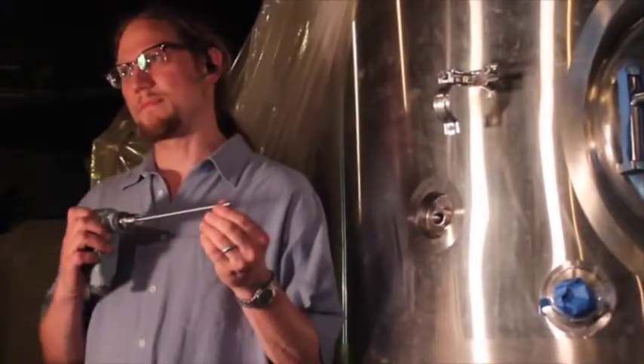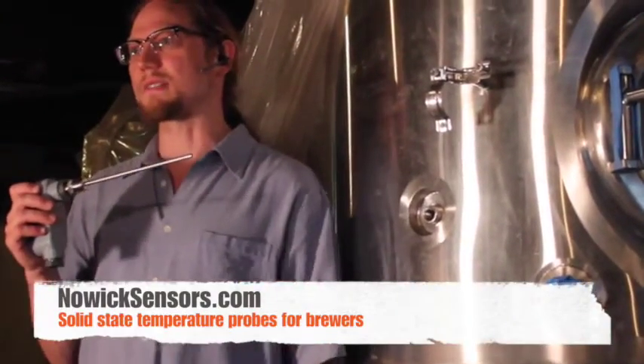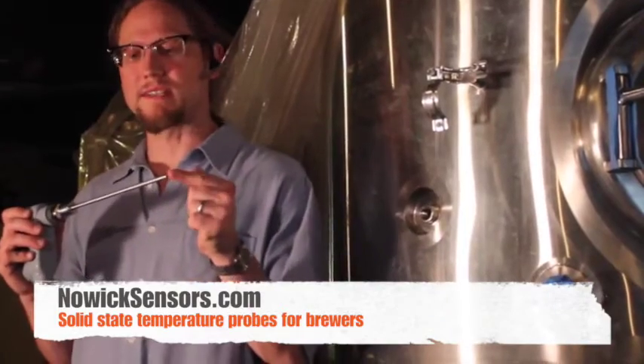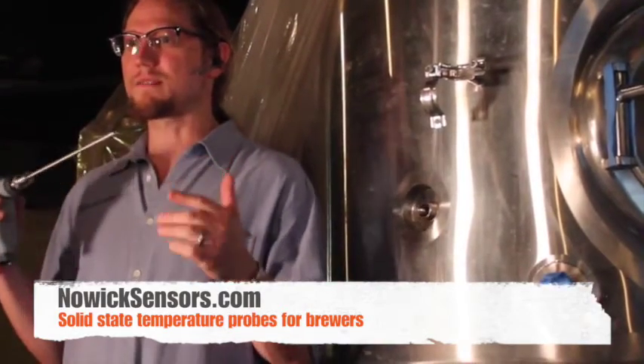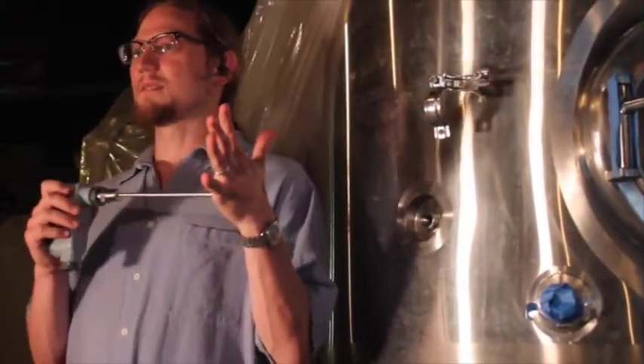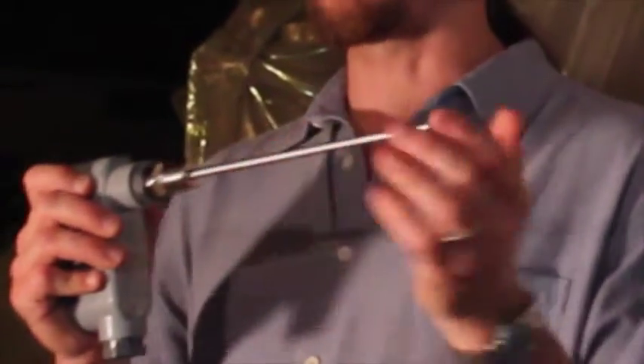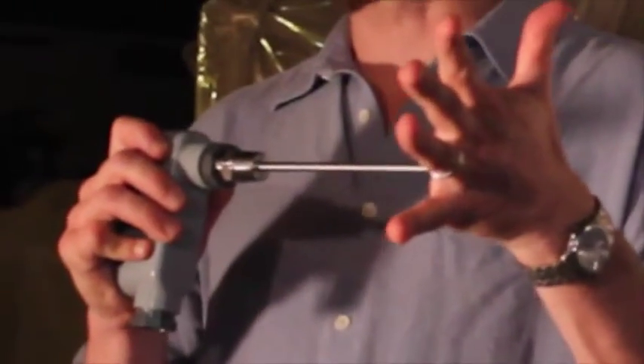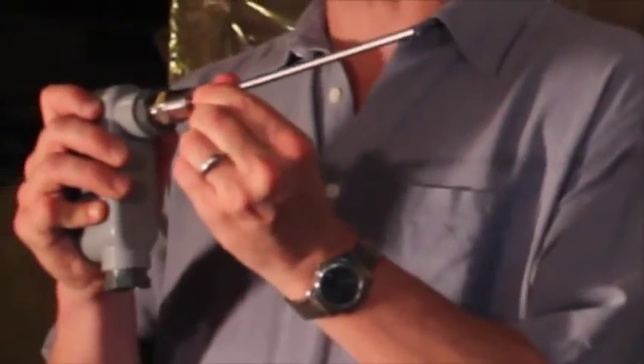Here's the temperature probe. In this case, it's a Nowick sensor solid state temperature probe. The sensing element is in the tip of the probe, so the end of the probe must be in good thermal contact with the bottom of the thermowell. This particular probe features a spring-loaded fitting that helps hold the tip of the probe against the bottom of the thermowell. Here you can see it moving by about half an inch to a quarter inch or so.